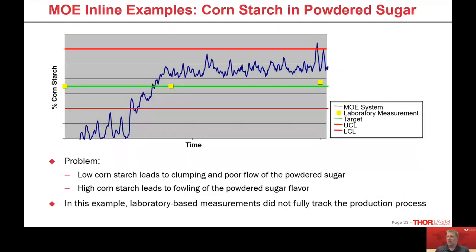We also looked at cornstarch in a powdered sugar production process. The routine lab measurement — specifically a turbidity measurement — was not able to detect rapid changes in the production process when relying on laboratory-based measurements at a defined interval. Low cornstarch leads to clumping and poor flow in the food product, while high cornstarch leads to dilution of the final flavor. Once again, the real-time performance adds quite a lot of value compared to what would be measured from a laboratory-based measurement.